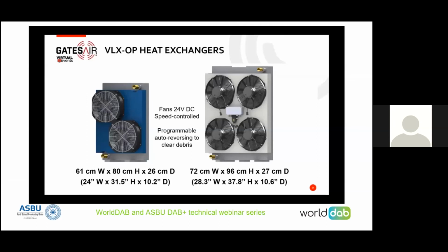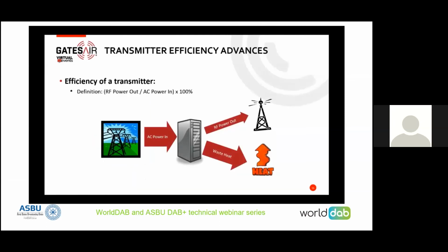Now, one thing that's quite unique in the system we offer is there's a programmable auto reversing that periodically will change the airflow to dislodge any debris that might get pulled in. So if you think of pollen and weeds and leaves and things like that, which normally you'd have to go to your transmitter site to make sure the heat exchanger is clean. This auto reversing allows them to be dislodged early, once an hour, a couple times a day, by reversing the airflow. It will clear that and help keep your system clean and operating very efficiently.